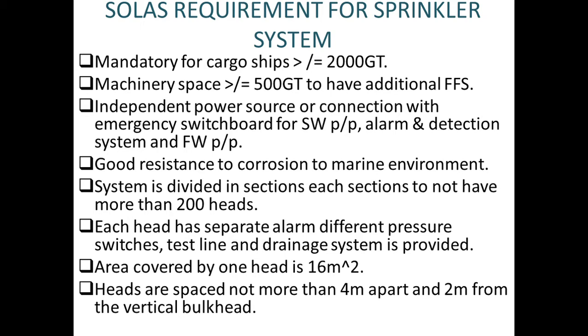they definitely will have this SOLAS requirement for sprinkler system for cargo ships greater than 2000 gross tonnage, GRT. Now when we talk about machinery space, if it is equal to or more than 500 gross tonnage, we need to have an additional firefighting system. We cannot solely depend on this sprinkler system. In addition to that, for machinery space, if it is more than 500, then we need to have an additional firefighting system.